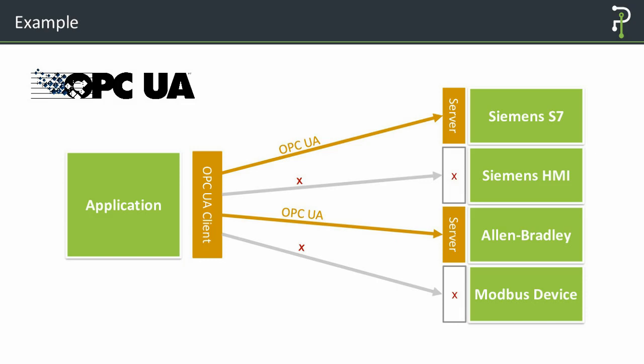I mean, the people working at the shop floor are usually quite clever and really good at solving problems. So what they will usually do is take one of the controllers to talk to the Modbus device, and then if the controller has data from the Modbus, it can give it over via OPC UA. But this is not such a clean solution, as for every change in that area, it needs a change on the machine, both the PLC program and the program you are running, which is not well encapsulated, as we would call it from the IT side.